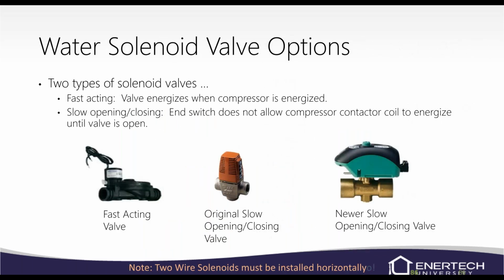Water solenoid valves, we have fast acting, the original slow opening, closing valve, and the newer one, which I would not use either of the 2 on the left. I would only use the one on the right. It's got the end switch on it, so it'll send that Y1 call through the valve. Once the valve is open, it'll send it down to the unit. So that way we know that the valve is open before we're starting up the unit.